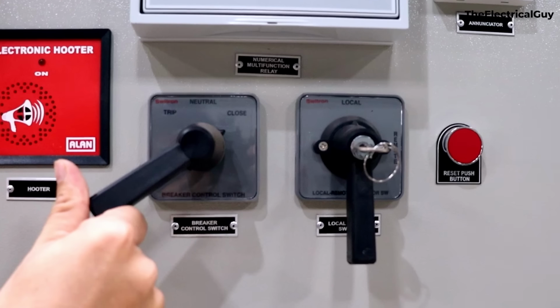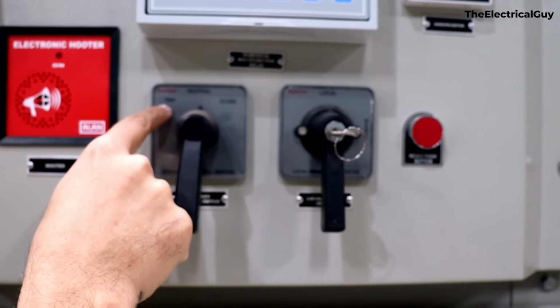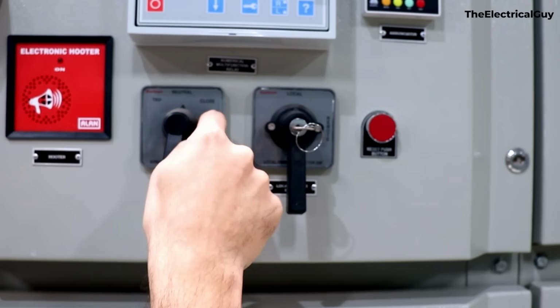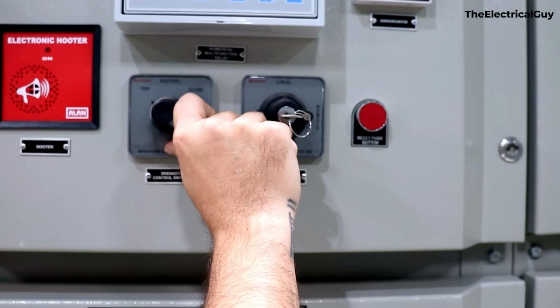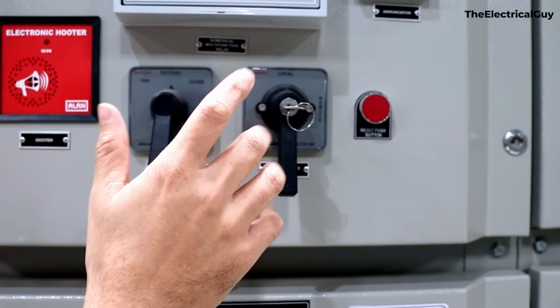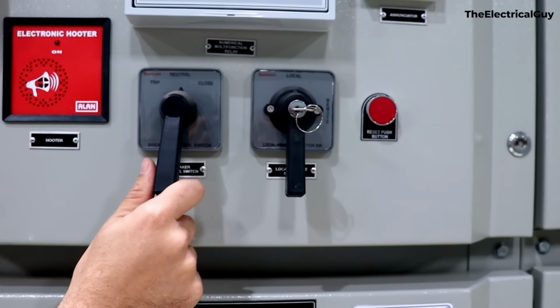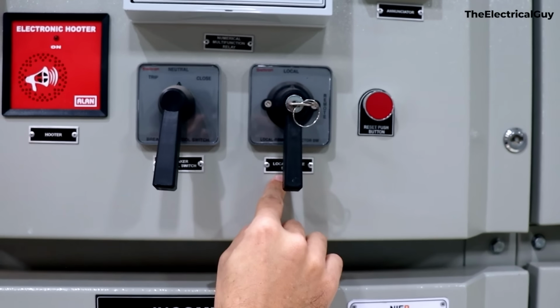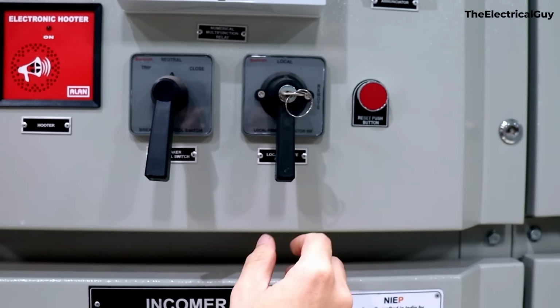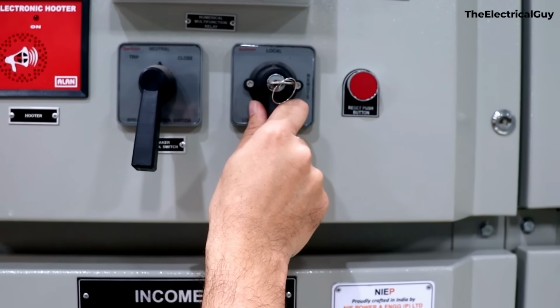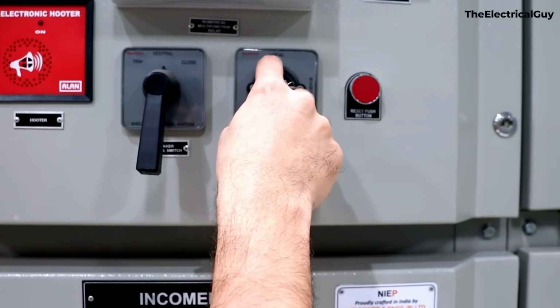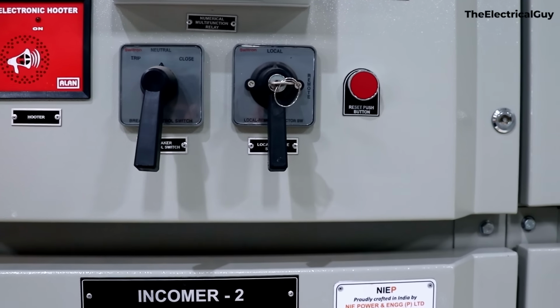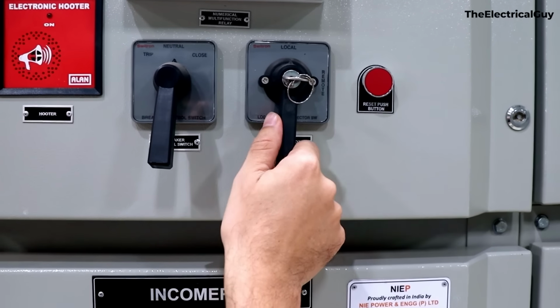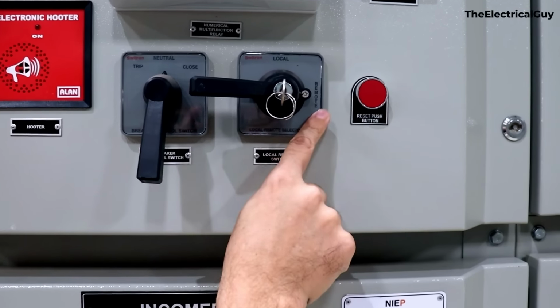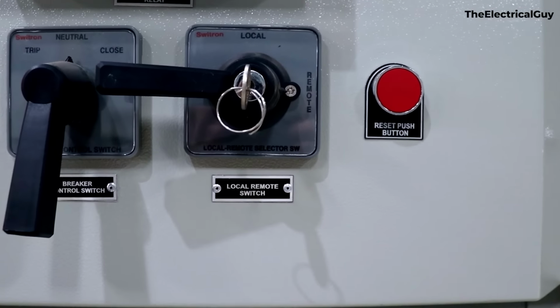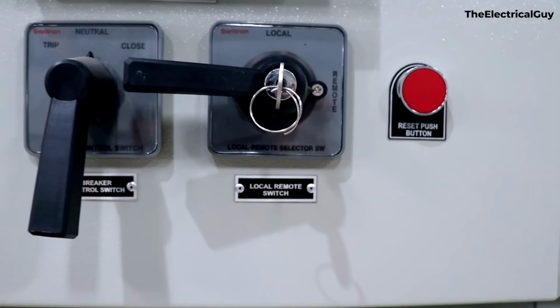And moving on, we have a breaker control switch. This is called the TNC switch. The reason is pretty obvious, because we have trip, neutral and close. If you want to trip, you can just turn it here. It will trip. This is the neutral condition and this is the close condition. And additionally, we also have a local remote selector switch. So in case you want to do a local operation, it must be on the local side of the indication. Then only you will be able to trip it locally. It's an interlock, we can say. If you want a remote operation, we just switch it back to the remote side and it will go to the remote operation where we can do a SCADA operation or from a control center.